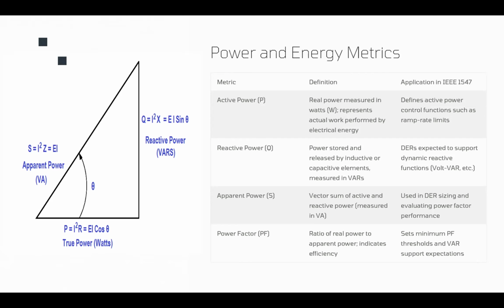We could have watt-VAR mode, where they adjust the reactive power based on the active power output. Or we would use reactive power in the constant reactive power mode, one of the modes defined by IEEE 1547, which allows a fixed reactive power injection or absorption to compensate for the system's need for reactive power. It mostly happens when we have a consistent load pattern, so we know how much reactive power we normally need. So we set it in a constant reactive power mode.